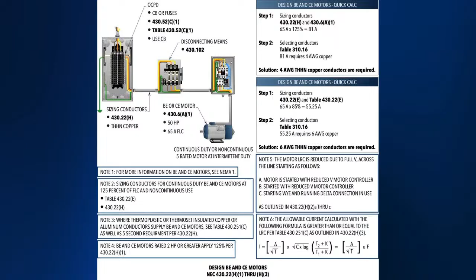And then you've got to look at all that other stuff, of course, and we're going to expand on that in the motor book. That's why I went back and showed this illustration, showing what the full load current is. I can tell you by looking at this, 50 horsepower, at 480 volts, or 460 as you might call it, would still be at 65 amps.